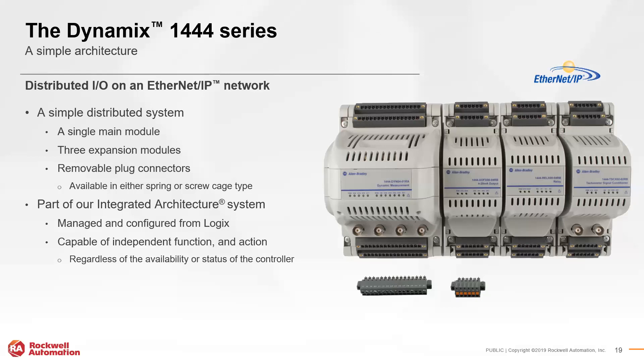The 1444 Dynamix System is Rockwell's on-machine condition monitoring solution for rotating equipment, featuring a simple distributed architecture. The bulk of computation and measurement is done within the large Dynamix Measurement Module. The 1444 system also has three expansion modules that make it a flexible solution for unique applications. Because it fits into Rockwell's integrated architecture, tags are tied directly to the system for configuration. It can communicate with the controller over Ethernet but is also capable of independent, standalone operation at the machine level.